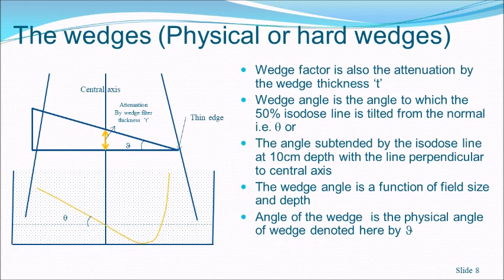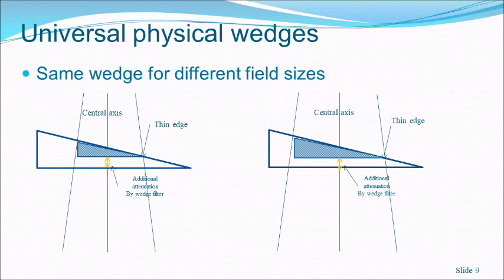The wedge itself has a physical angle — the angle of the wedge — which produces a tilt in the isodose line. Do not confuse the angle of the wedge with the wedge angle; the wedge angle is what matters for treatment planning. In older cobalt unit days, wedges were made for various field sizes, but later it was understood that one large wedge, perhaps 15×20 cm, could serve as a universal physical wedge for smaller field sizes as well.